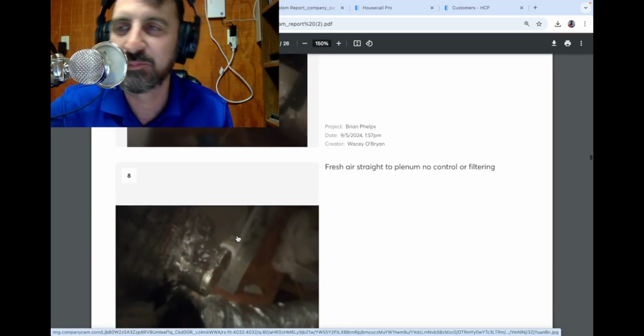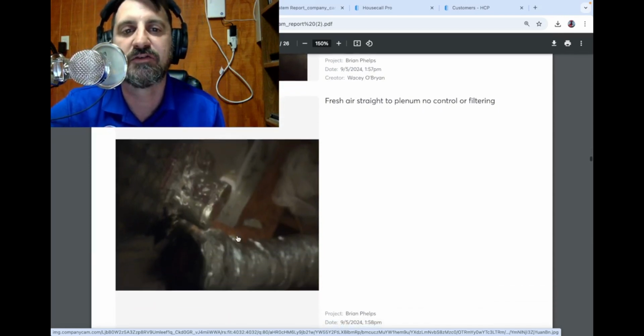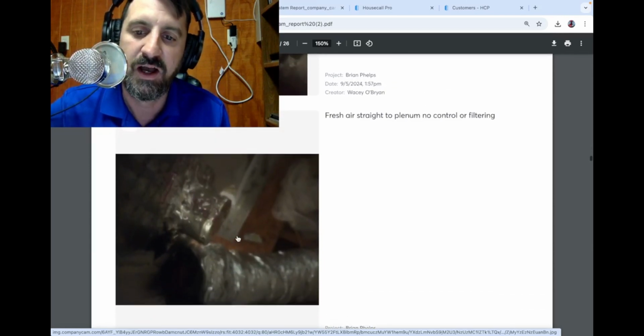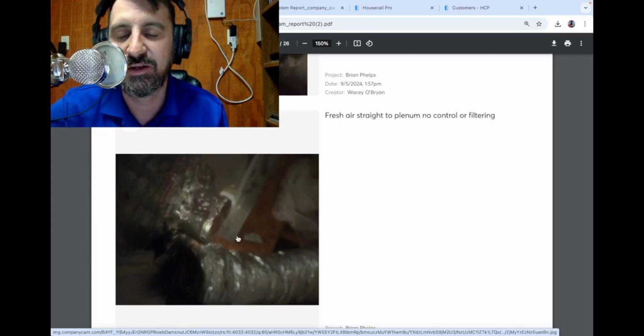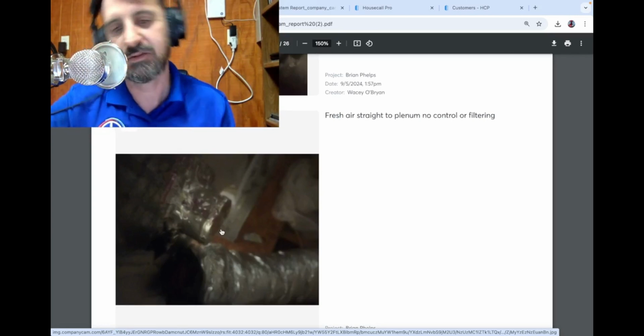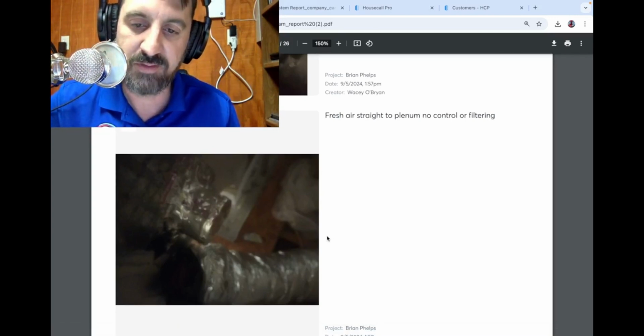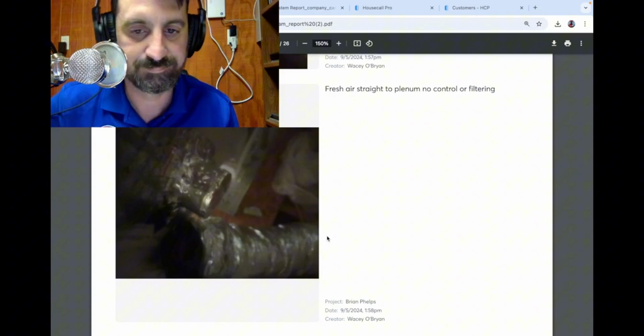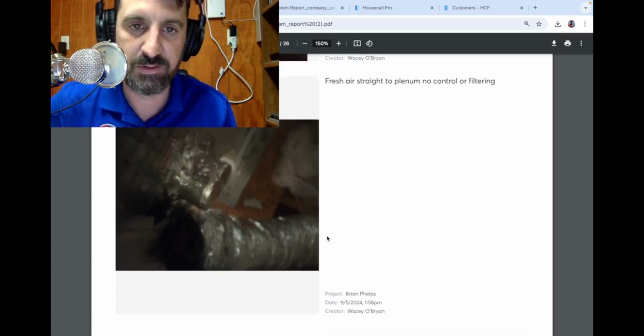I know there's people out there that are going to go off on using flex ducts in general, let alone having turns in it. But bottom line, if you take a CFM test and you're getting the CFM you're supposed to be getting, then, you know, that's what it is.